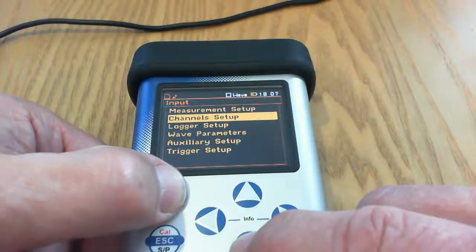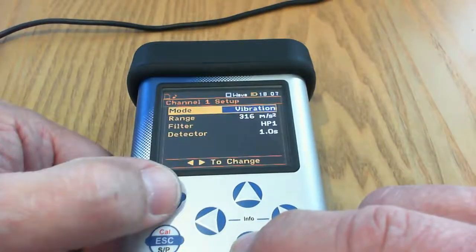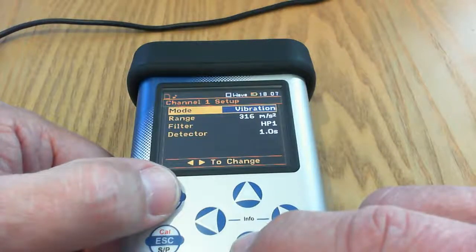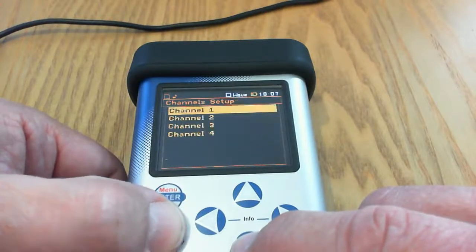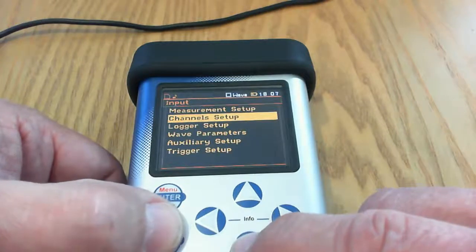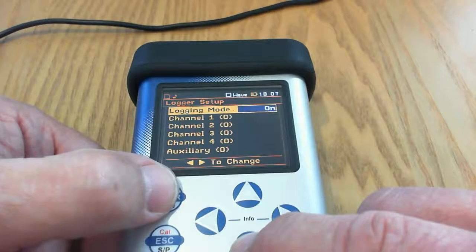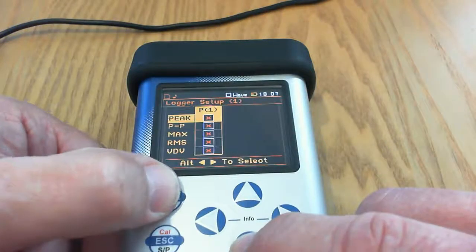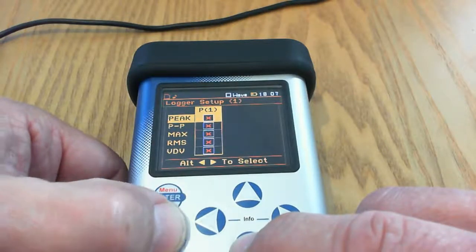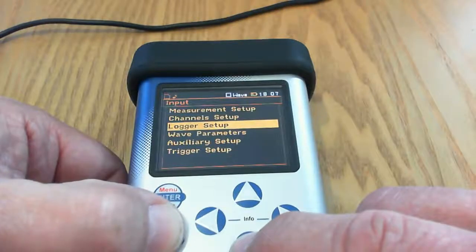If we're happy with all those settings press enter. Channel setup, as I said before, you can set this up for vibration or sound and change the range and change the filters. We'll skip over that for now. If you want to use the logger, simply make sure that it's switched on and then you can choose which parameters you want to go into the logger. But again I won't worry too much about that.